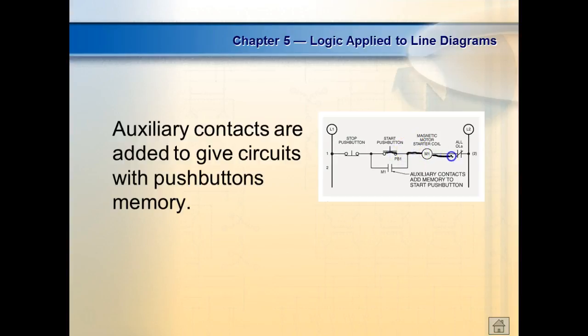It's going to energize M1. M1 says I have a contact in what? Line 2. I'll look at line 2. There it is. So what's going to happen? It's going to close. Now what can you do with the start button? You can let it go. Now this thing is sealed in. How long is it going to be sealed in? Well, two things will unseal it. One is power fails. And this is why this circuit is so popular, because it's safe.